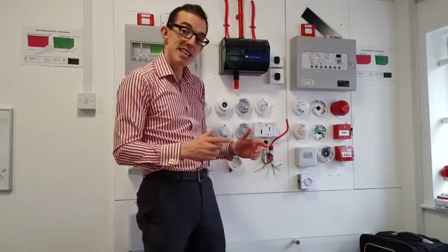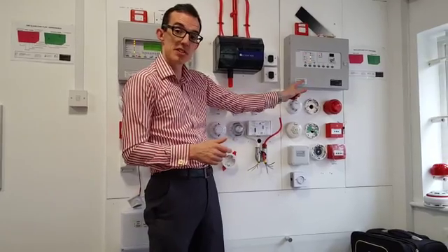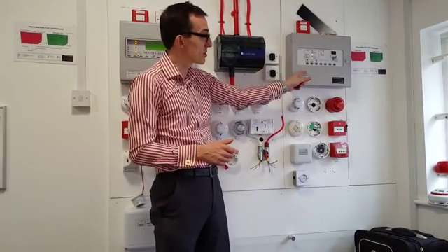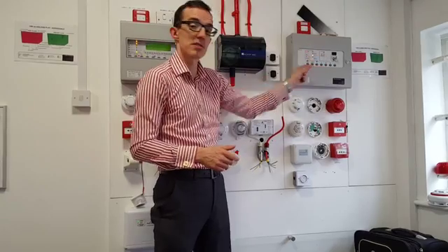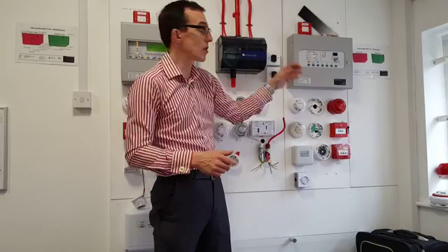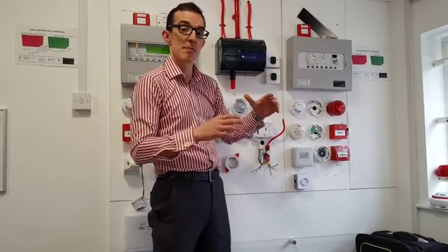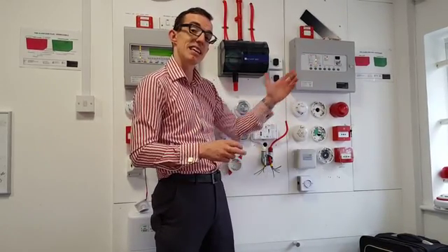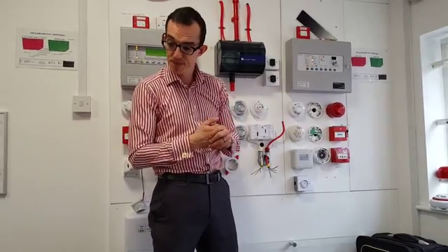So continuing on with the ABC theory of learning, we're going to talk about C, which is conventional. So we mentioned it yesterday. So this is a conventional system. A conventional system is different to an addressable system because it doesn't have a screen. So the only thing a conventional system can do is give you information on a particular zone. So that could be the whole of a floor, or two parts of a floor, or the whole of an area. But it won't be specific, it won't give you a postcode. So I mentioned more about that in the hands-on training, but for this video, C is for conventional systems.